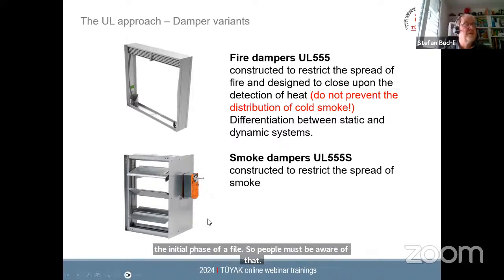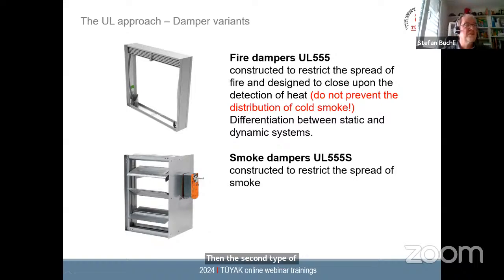Then the second type of damper, which is used quite often, is so-called smoke dampers. These are referenced to the standard UL 555S. S is for the smoke. You see it here, it's a different construction. It's a motorized construction. They are sometimes made of steel plate, of steel, but also of aluminium. They have the duty to prevent the spread of smoke. So they have a limited leakage rate, etc.